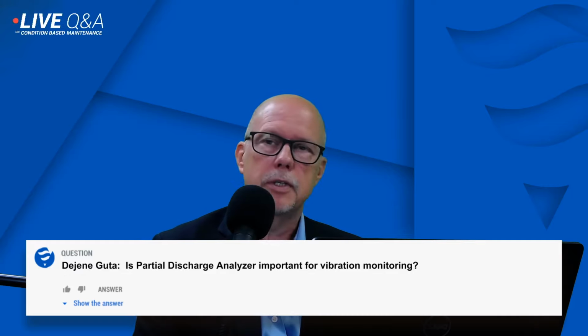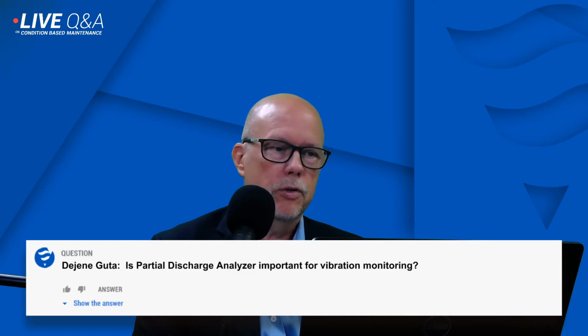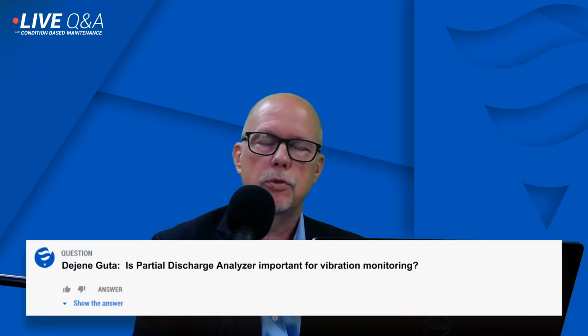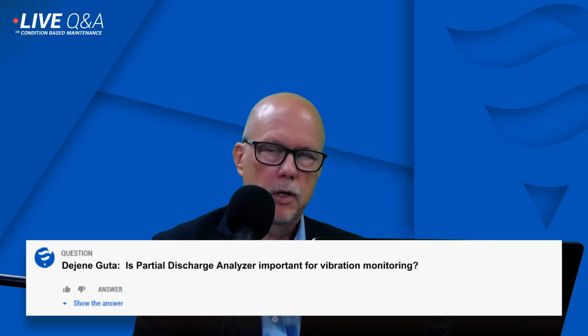But the slot discharge is there because there's damage now. It's probably been vibrating for some time, and now you're at a point where you can see the slot discharge caused by the damage to the insulation. You're losing contact between the insulation and the core, and it's starting to discharge. So we strongly believe that's a much better approach: to detect vibration early on and fix it before you have damage to the insulation.